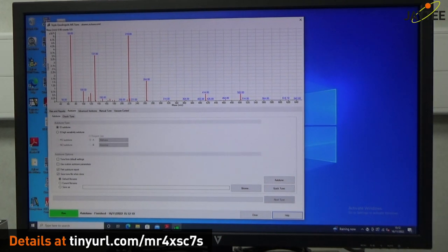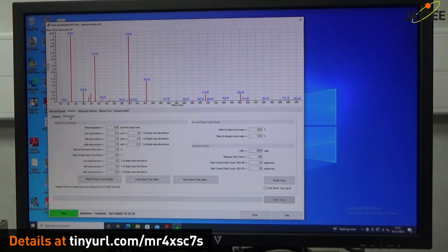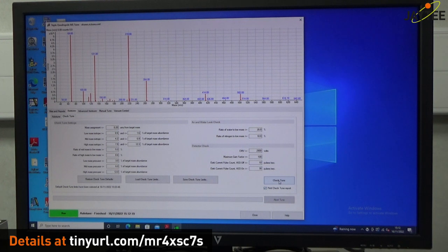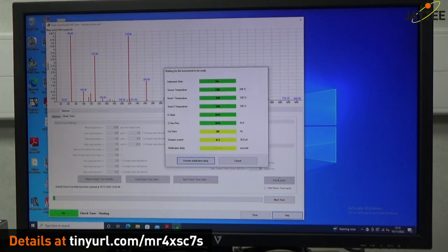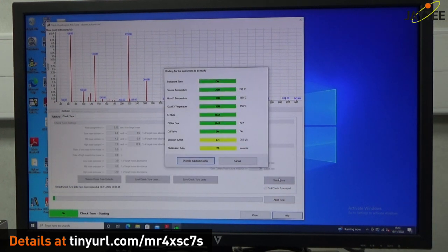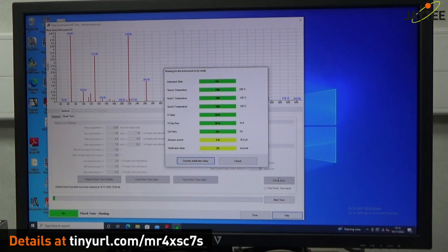And then what we're going to do now is we're going to do the check tune. So this tells you then I'll go and print it out, which is optional. And we'll do the check tune and that will just confirm that everything is in order and everything will just say okay, okay, okay. And again, I'll attach this data to the information that's sent out to the instrument.